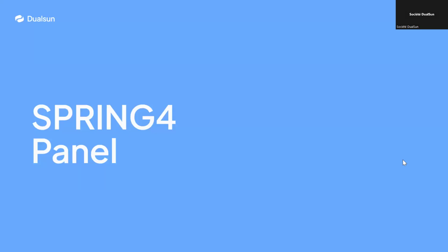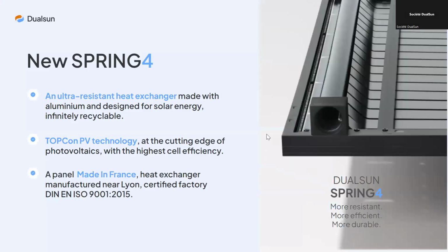So much for this brief reminder. I'd now like to move on to the Spring 4 hybrid panel and show you the specific features that led to the design of the product and the essential improvements that have been developed. First of all, our new Spring 4 panel is an ultra-strong aluminum heat exchanger specifically designed for solar energy and aluminum that can also be recycled ad infinitum. This was an essential element. It has to have a product in a material that is robust and that can react well to use that is not always according to the rules.